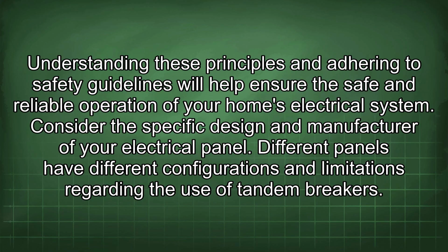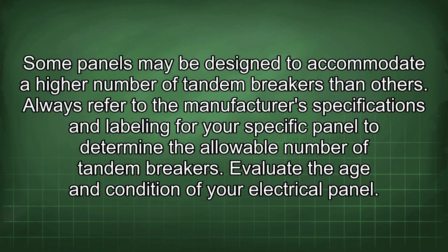Different panels have different configurations and limitations regarding the use of tandem breakers. Some panels may be designed to accommodate a higher number of tandem breakers than others. Always refer to the manufacturer's specifications and labeling for your specific panel to determine the allowable number of tandem breakers.